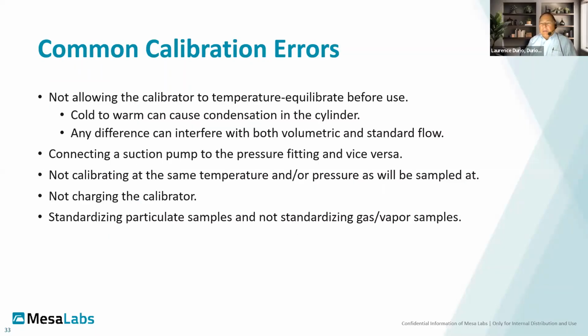Errors that we see, big one, taking a calibrator, particularly out of cold into a warm atmosphere. Everybody's gone out, come in from outside in the wintertime, and you've had your glasses fog up. Well, the same thing will happen inside your calibrator, except when that happens and you use a piston prover, the piston will pick up that moisture and there's a good chance it will stick. And as I said, it will not normally clear. It's a trip back to the factory.